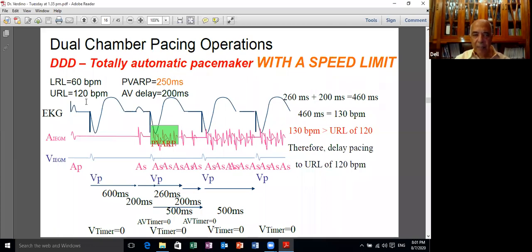So under these circumstances, you can see that there is an obligatory delay in ventricular activation after sensing the atrial activation. As you increase the atrial rate, this delay can transform from a first degree delay, which is a delay in the AV junction, into a pseudo-Wenckebach, or into a 2-to-1 block. All of these are normal activities for a dual chamber pacemaker. Now, it's important to understand these things.